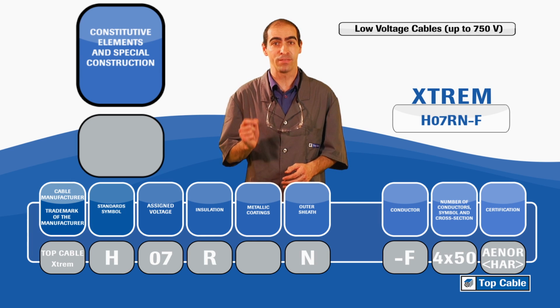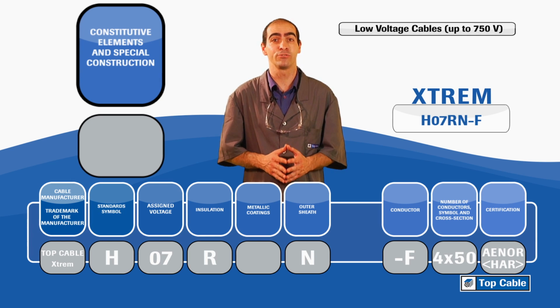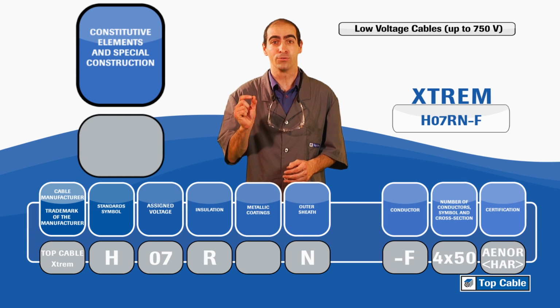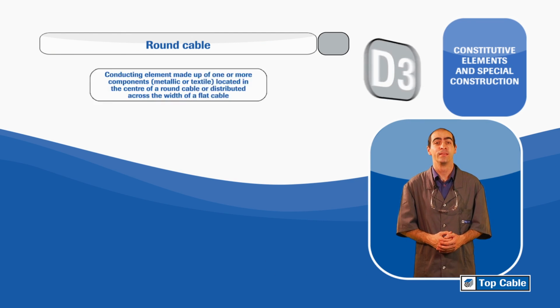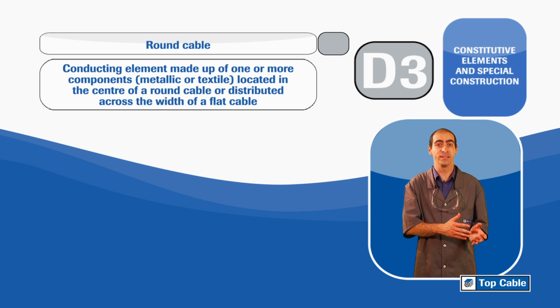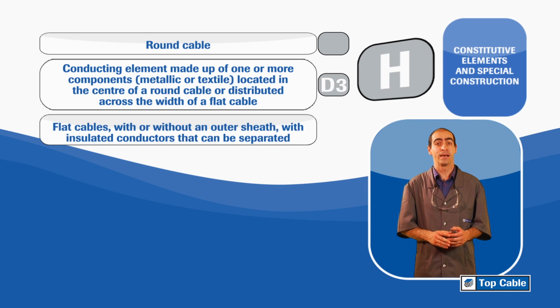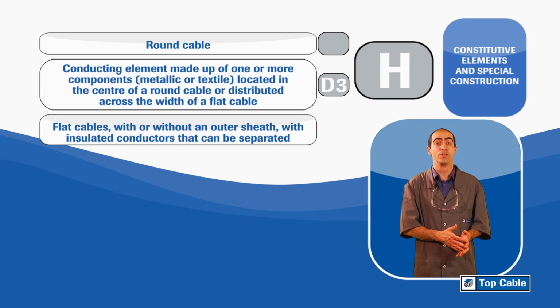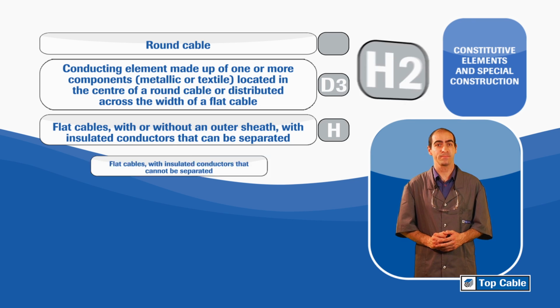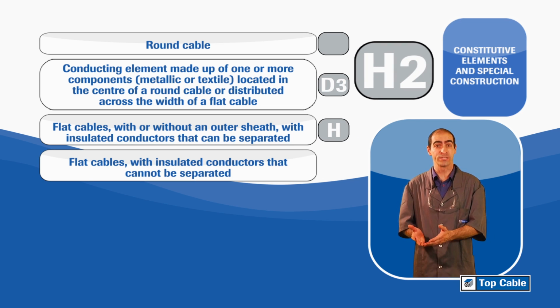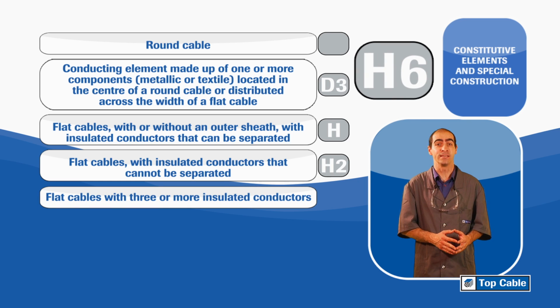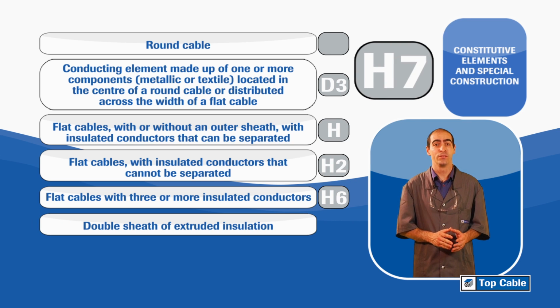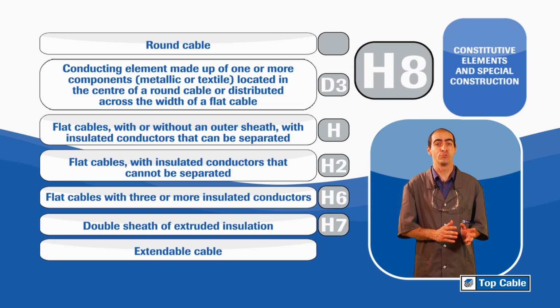Xtrem H07RN-F is a round cable. Other possibilities are none, round cable, D3, conducting element made up of one or more components, metallic or textile, located in the center of a round cable or distributed across the width of a flat cable. H, flat cables, with or without an outer sheath, with insulated conductors that can be separated. H2, flat cables with insulated conductors that cannot be separated. H6, flat cables with 3 or more insulated conductors. H7, double sheath of extruded insulation. H8, extendable cable.